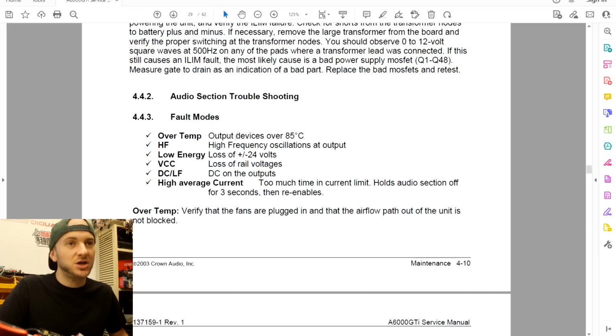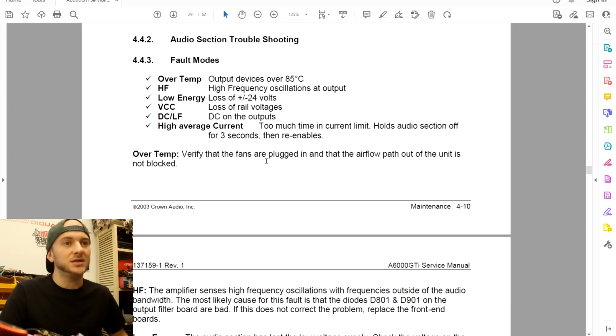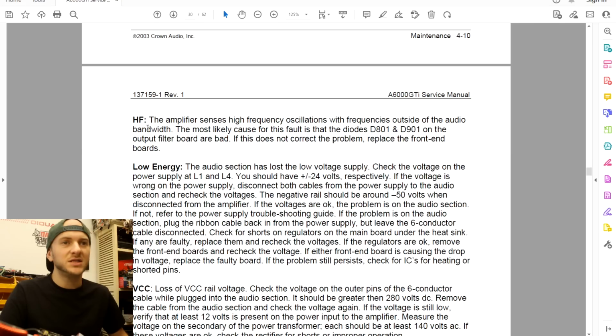We've got over temperature, high frequency oscillations at output. I'm not sure what would cause that, but that's pretty interesting actually. That has that kind of protection mode: loss of the plus minus 24 volts, loss of the rail voltages, DC on the output terminals, and too much current.